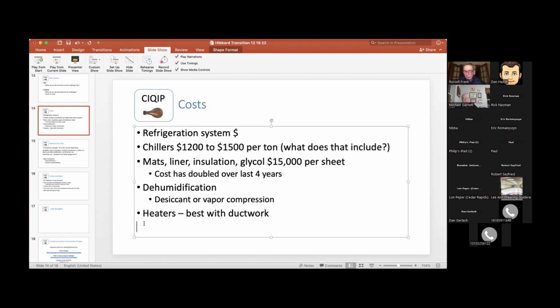We've got 2 questions. One from Dan, which basically has to do with, what's the electrical service you need? How many amps? Well, it depends on your chiller, how big your chiller is, because that's 80% of your electric. A 60-ton chiller, you're going to need about 400 amps. 3-phase? Yes, that's preferable. When you start going over 7.5 horsepower, you want to be in 3-phase because the starting load is astronomical, and if you happen to have a demand meter, that'll kill you. So you always go with 3-phase on anything. Any of the larger equipment is always going to be 3-phase.